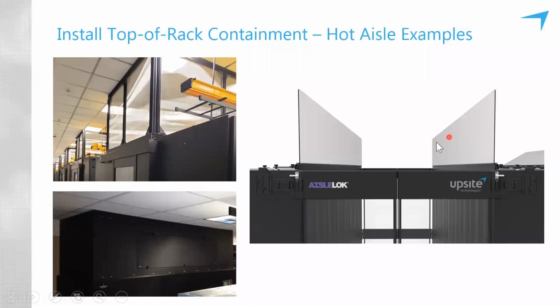Once you get it moving in the right direction, and if the ceiling plenum is being used for a return, and the return air registers in that drop ceiling are appropriately placed, then this partial hot aisle containment solution can easily get you 80 to 90% of the benefits of what a fully enclosed hot aisle containment solution could get you. These baffles are also modular in that there's one per cabinet, and they're sized to match the width of the cabinets.